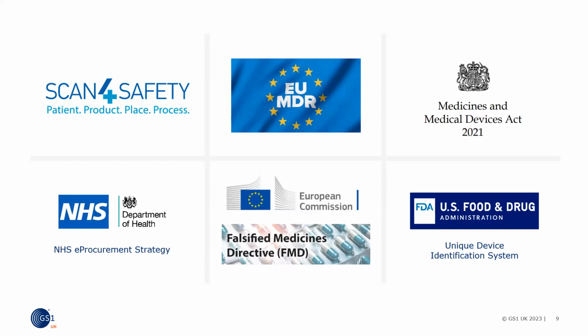In the US, the FDA introduced legislation for the unique device identification of medical devices. The GS1 system is by far the most prevalent of the barcoding standards that are used for medical device identification. This was followed by the EU medical device regulations, and GS1 standards work in the same way, which is the benefit of using standards. You don't have to change what you're already doing for different markets. The Medicines and Medical Devices Act in the UK provides a platform for medical device regulation to be implemented in the UK. More on that to follow from the MHRA.